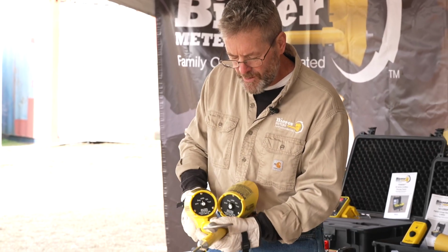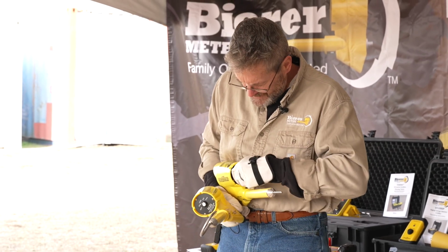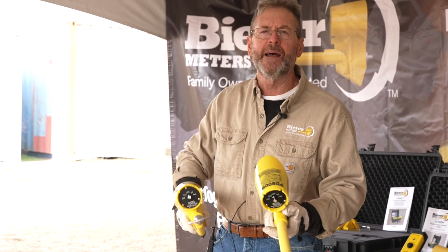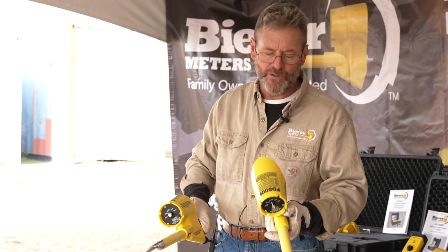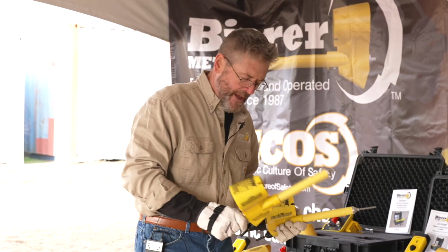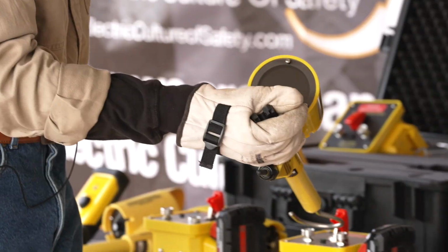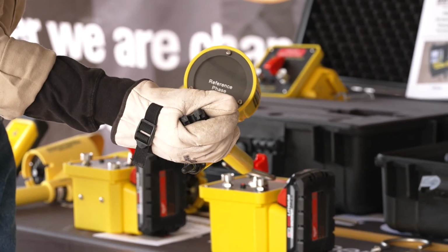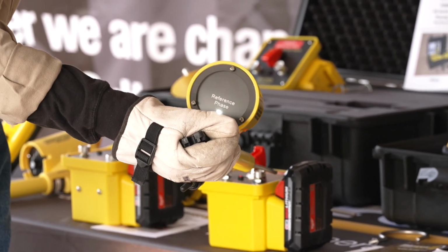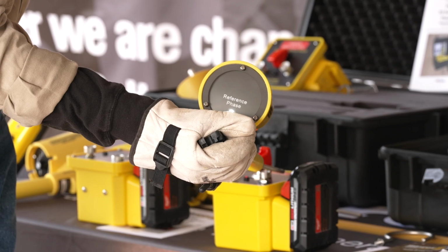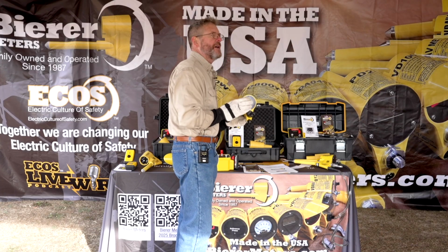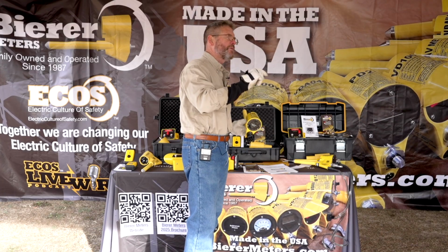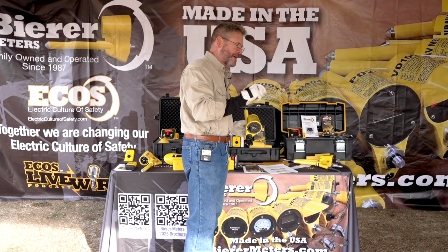So you're going to go to URD on both tools, and you can test one tool at a time or together. Let's test one tool at a time. You've got your reference probe, and you should see a white light. It's hot or not — it's just telling you that the tool's working properly as a hot-or-not tool, that this conductor is energized and the tool's working properly as a reference probe.